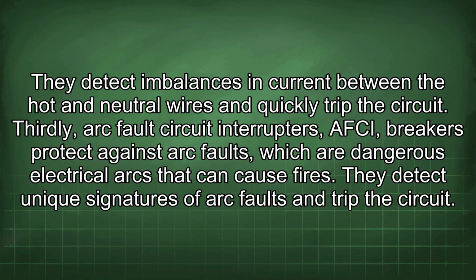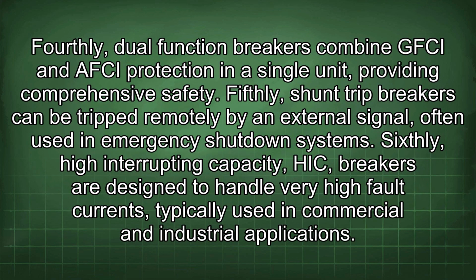Thirdly, arc fault circuit interrupters (AFCI) breakers protect against arc faults, which are dangerous electrical arcs that can cause fires. They detect unique signatures of arc faults and trip the circuit. Fourthly, dual-function breakers combine GFCI and AFCI protection in a single unit, providing comprehensive safety. Fifthly, shunt trip breakers can be tripped remotely by an external signal, often used in emergency shutdown systems. Sixthly, high interrupting capacity (HIC) breakers are designed to handle very high fault currents, typically used in commercial and industrial applications.